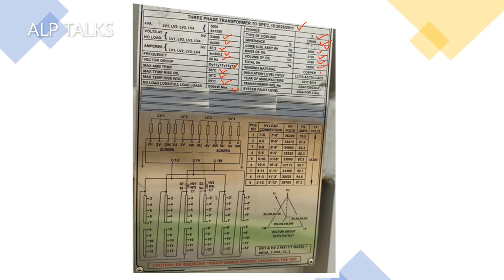Winding material is copper. We have insulation levels here: as it is 33 kV, we have 170 kV BIL and 70 kV power frequency. Similarly for LV we have 3 kV power frequency. Generally for LV we don't have any BIL requirements. Here we have the serial number, and last we have the system fault level: 25 kA for 3 seconds. We have to take care of all the external equipment — bushings, bus bars, and all. So here is the template of the transformer.